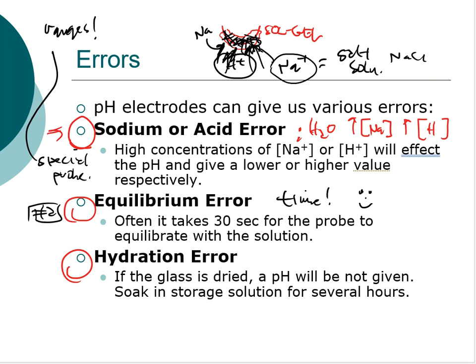The time needed depends on how drastic the pH change is. If you're measuring pH 7, then pH 3, the probe has to reach across a big range and that takes time — it doesn't happen instantaneously. The best way to fix this is simply be patient: wait about 30 seconds before taking a measurement. That 30-second window is built into most pH meters, shown as a smiley face, 'OK', or a small dot depending on the manufacturer.